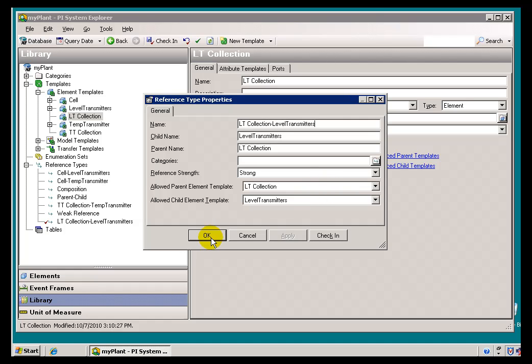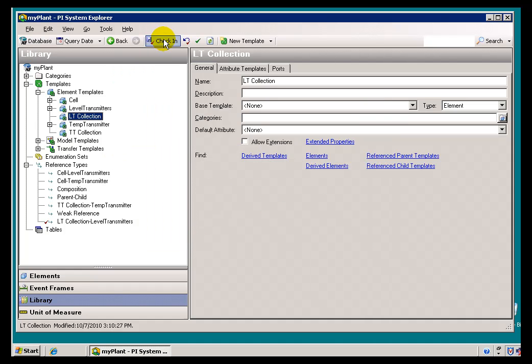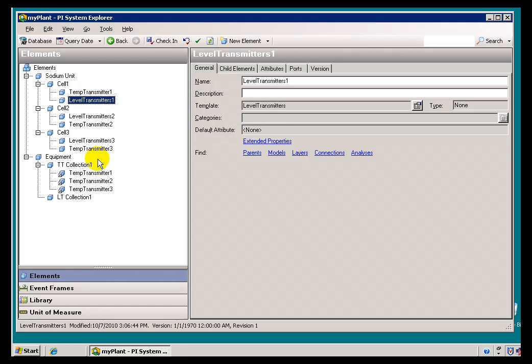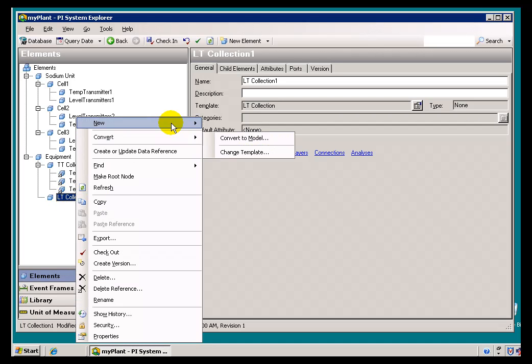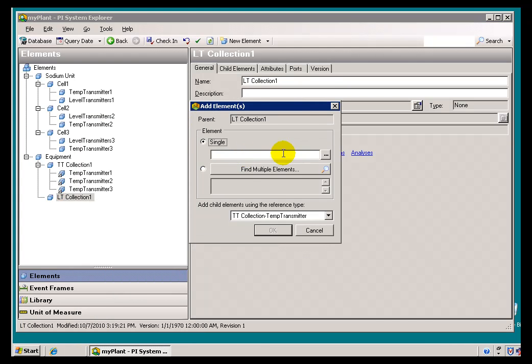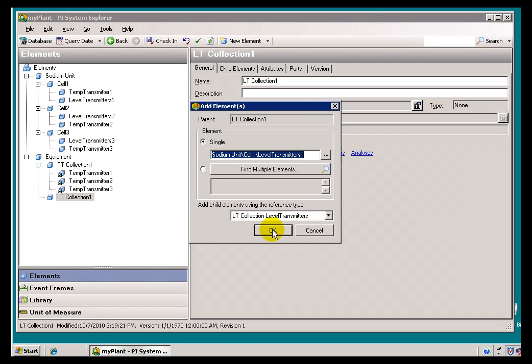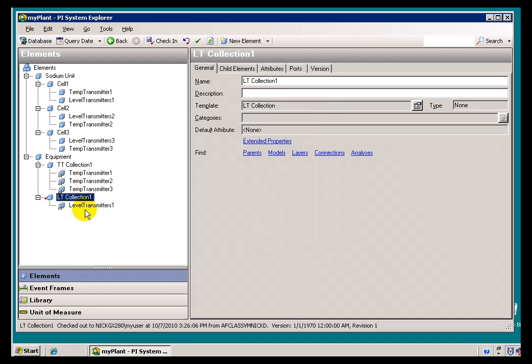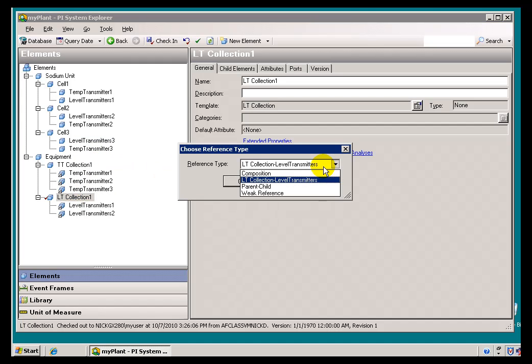I don't need to edit the Template, so I'll go ahead and Acknowledge, check all this in, and now back at the Elements level I can either drag and drop or add an Element Reference. Let's add an Element Reference, then we'll drag and drop. Right-click here — we're going to add References to Level Transmitter 1, 2, and 3. We can find multiple at this point. Here's my Level Transmitter — notice the list of Reference Types available, and the one we just created is what I want. I'll also drag the remaining Level Transmitters using that Default Reference Type.